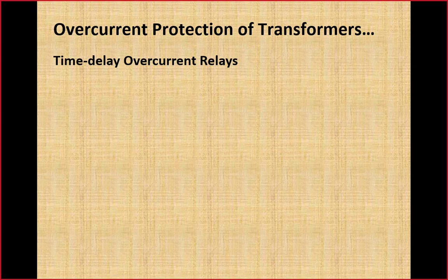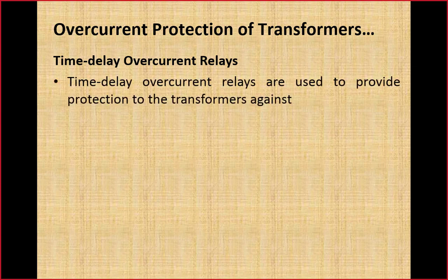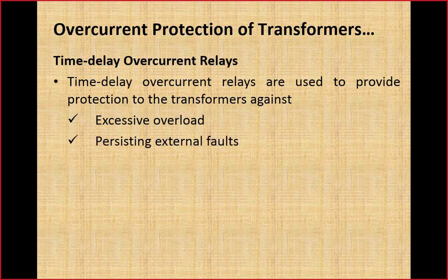Now here comes the time delay over current relay application for the transformer. Remember, transformers installed in substations have this time delay over current relay protection. The over current relay is used to provide protection against excessive overload conditions and persisting external faults.